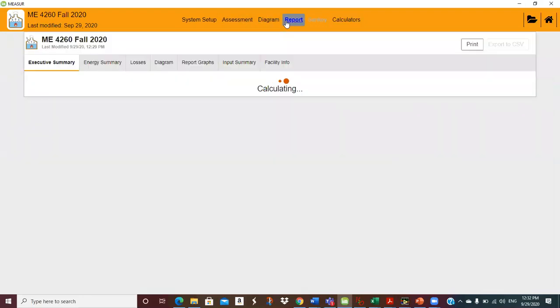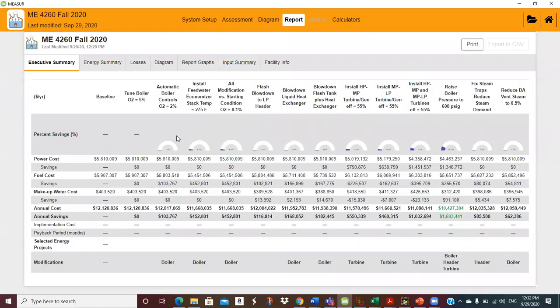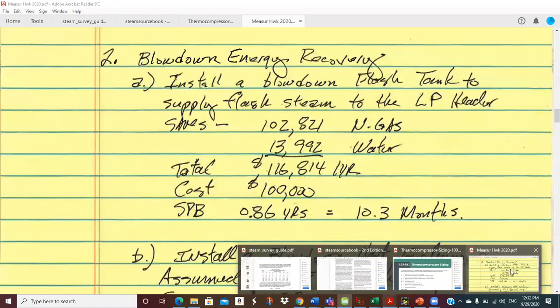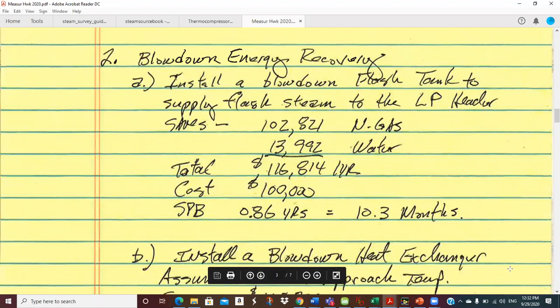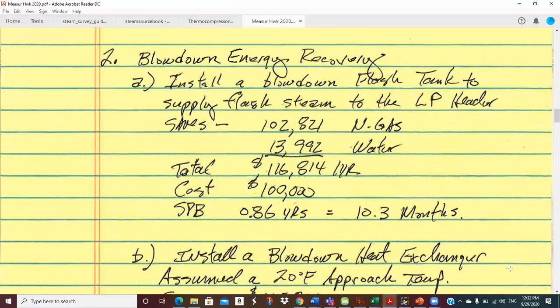So we can look at report — flash blowdown to low pressure header. This is saving natural gas: $102,821, and we're getting almost $14,000 in water savings because that steam is water that was being thrown away — it stays in the system so we don't have to buy as much makeup water. Those numbers look the same, so the total is about $116,800. You could do that for $100,000 for sure. Those blowdown flash tanks are not terribly big. That's a really nice project.